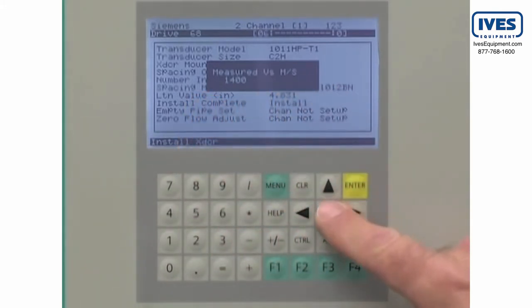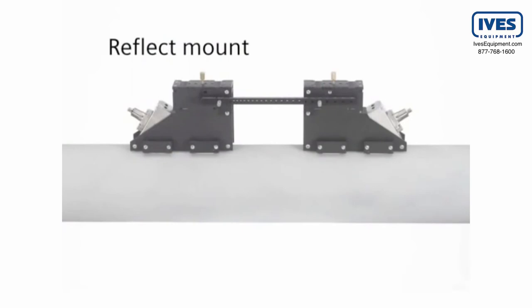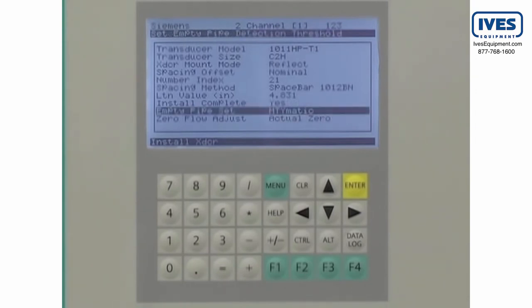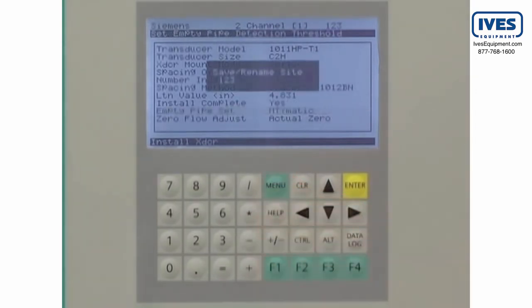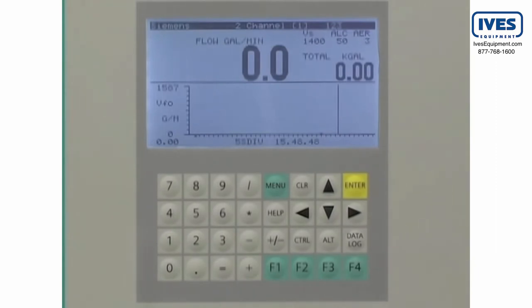Press the down arrow to continue. The Siemens FUS-1010 will automatically begin the Auto-Zero routine. The Auto-Zero routine is only for applications where the sensors are mounted in reflect mode. When the Auto-Zero is complete, the flow meter is ready to measure flow. Press the menu key; the FUS-1010 will prompt you to save the site data, providing a backup for future use or recovery. Press the right arrow and enter key to save the site data.